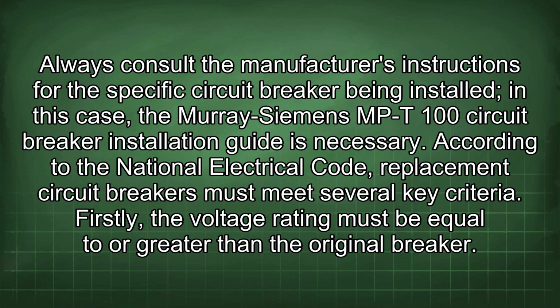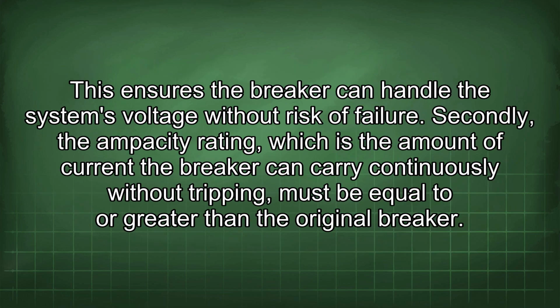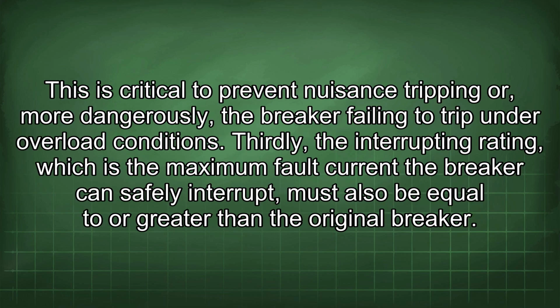According to the National Electrical Code, replacement circuit breakers must meet several key criteria. Firstly, the voltage rating must be equal to or greater than the original breaker. This ensures the breaker can handle the system's voltage without risk of failure. Secondly, the ampacity rating, which is the amount of current the breaker can carry continuously without tripping, must be equal to or greater than the original breaker. This is critical to prevent nuisance tripping or, more dangerously, the breaker failing to trip under overload conditions.